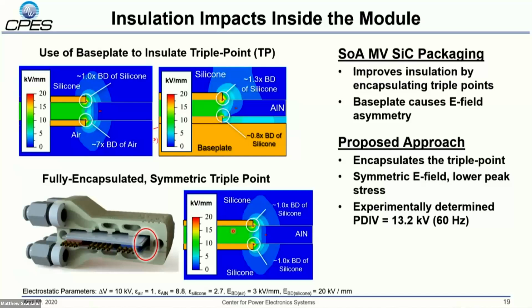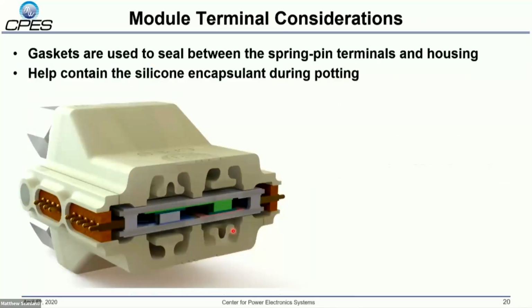And this has been experimentally verified. I partial discharge tested these substrate samples at our lab in the basement of Whittemore, and found that we were able to achieve about 13.2 kV PDIV at 60 hertz on these substrates, sufficient for 10 kV operation.